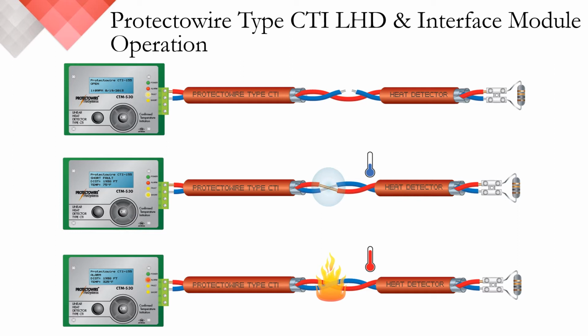I want to pause and focus on the middle image on your screen here, because this image is what really separates our CTI technology from all other digital linear heat detectors. As I mentioned earlier, using our CTM series interface modules, we can determine the temperature at any shorted point on a CTI detector. This middle image represents a CTI detector that has been damaged. It's been bent beyond its 90-degree bend radius, it's kinked, smashed, etc. When our CTI series detector is mechanically damaged, our CTM module will actively display the location in feet or meters, as well as the current temperature at that shorted point. So for refrigerated and freezer warehousing, this feature is undeniably important.